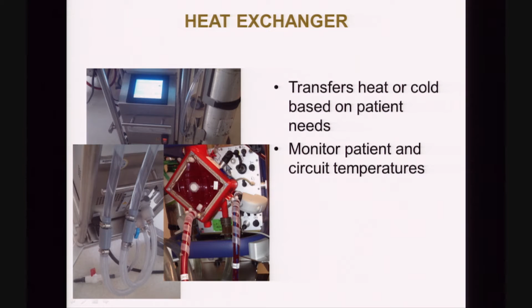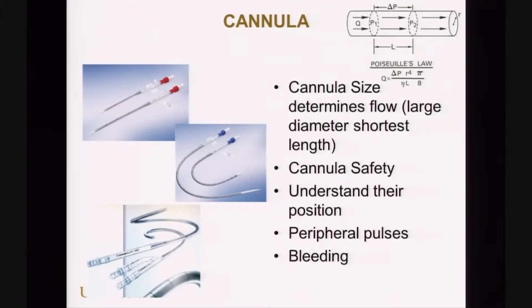How do you get it in and out? Obviously, you need cannulas in the patient. These are large cannulas. There's no messing around here. Your venous cannula is generally a 25 to 28 French cannula. And if you're going back into the arterial system, you're using an 18 to 19 French cannula in the artery. If you're using a double lumen cannula, which I'll show you in a little bit, those are 31 French. So they take a little bit of work to put in, and the safest way to do it is under fluoroscopy. The tubing is, again, heparin bioline coated, which minimizes the inflammatory reaction and also reduces the amount of anticoagulation.